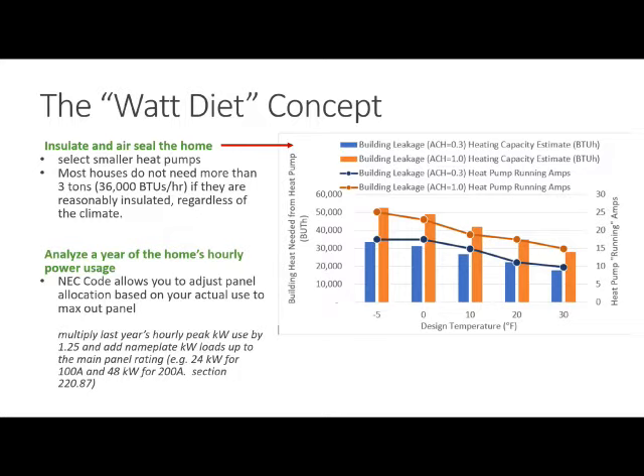This figure shows different design temperatures and heating needed from the heat pump. The blue is with a tighter building shell, and the orange bar is with a more leaky building shell, measured as air changes in a non-pressurized house. So reiterating that point, a tighter building will need less heating, meaning you can have a smaller heat pump, which results in less amps and less power used.